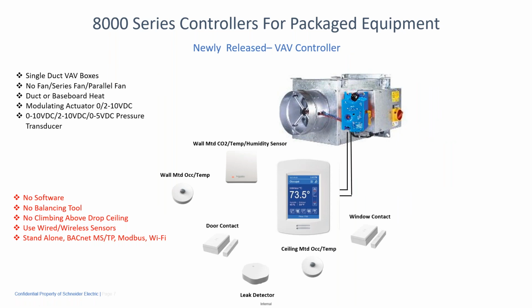Recently, we've released a controller that does VAV boxes, either pressure independent or pressure dependent, right? So single duct VAV boxes, you can have a fan on those, or you can do no fan, or you can do a series fan, or you can do a parallel fan. It supports duct or baseboard heat or both. Modulating actuator on the damper actuator, and then input from a pressure transducer corresponding to the pressure range, and then an output to a modulating actuator.